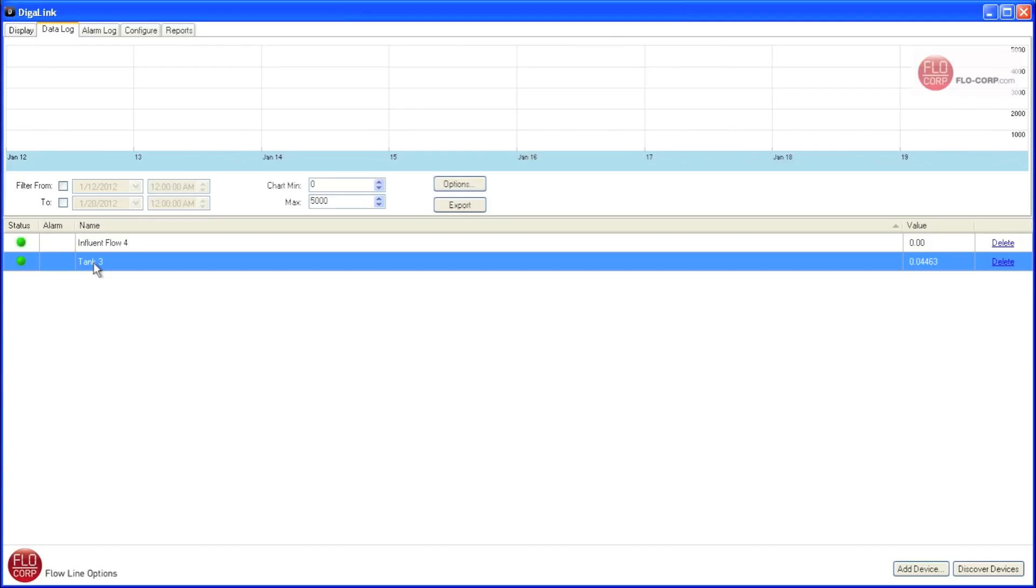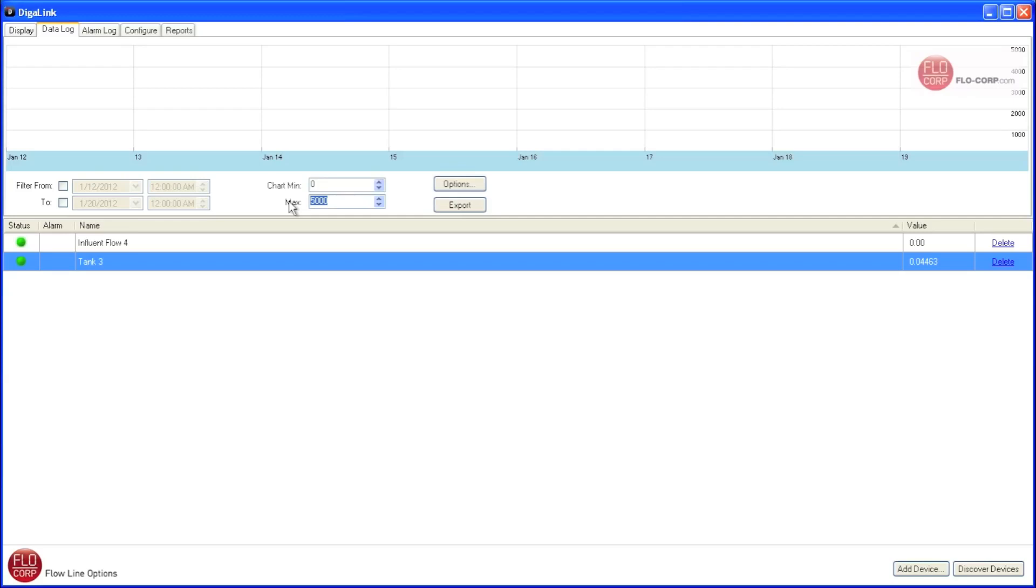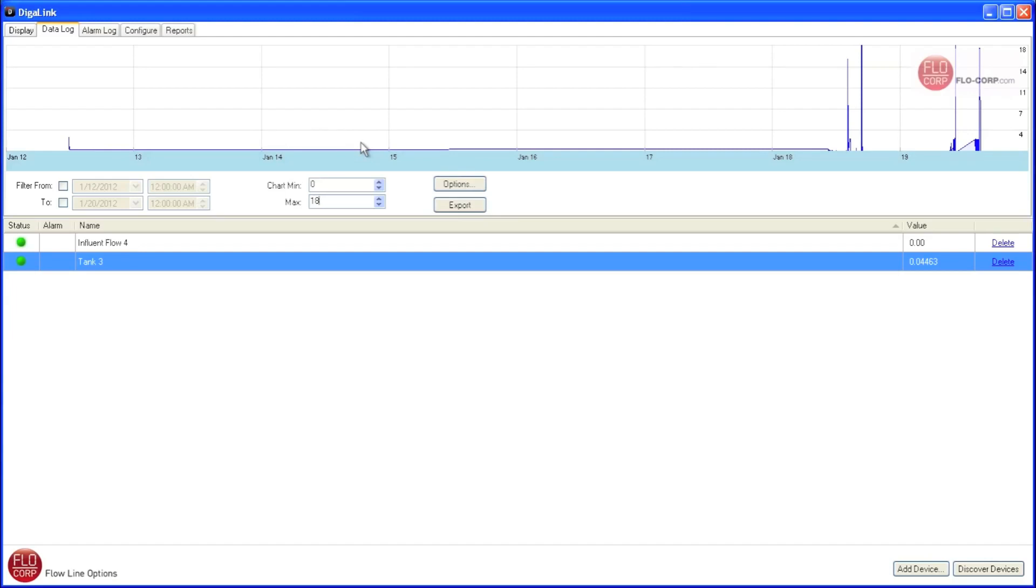Now it doesn't really look like we're charting anything, but that's because our chart has a different scale than our device. The Tracer 1000 is scaled for 0 to 18 inches. And our Tracer 1000 is connected to our DigiCom 2000, which is what we're monitoring here with Tank 3. I'm going to change our scale to be from 0 to 18. And then we see our charted data up here. Now we have a very interesting trend because this is a demo for tank level. It looks like our tank is very low and then has some very high, very quick spikes.